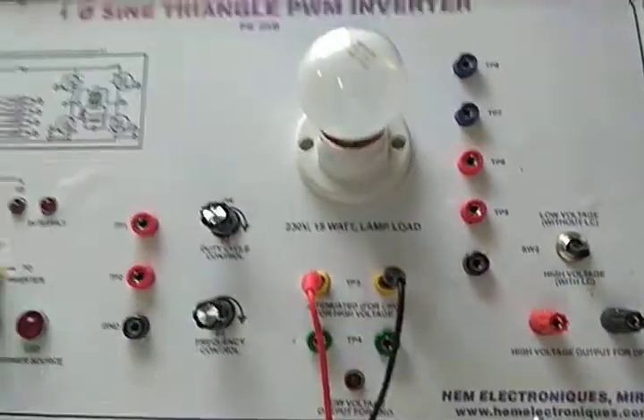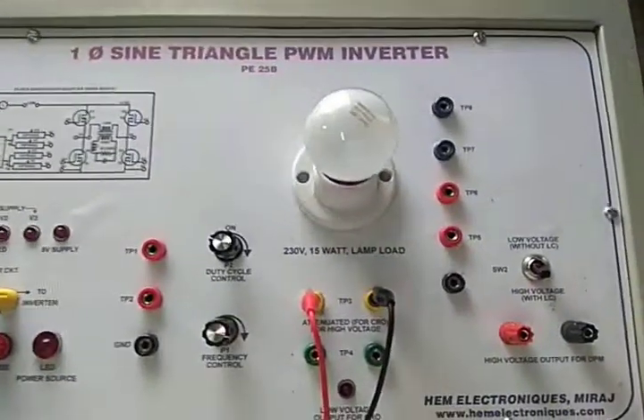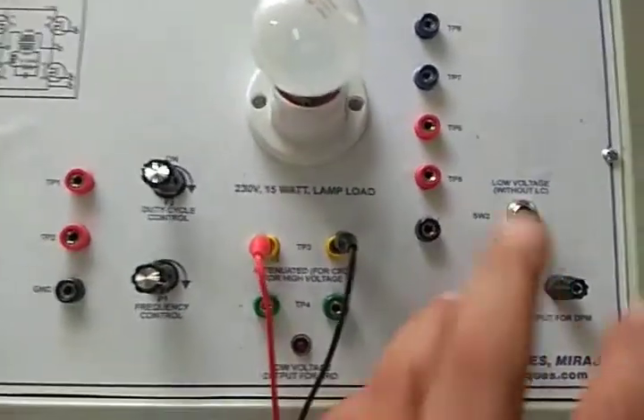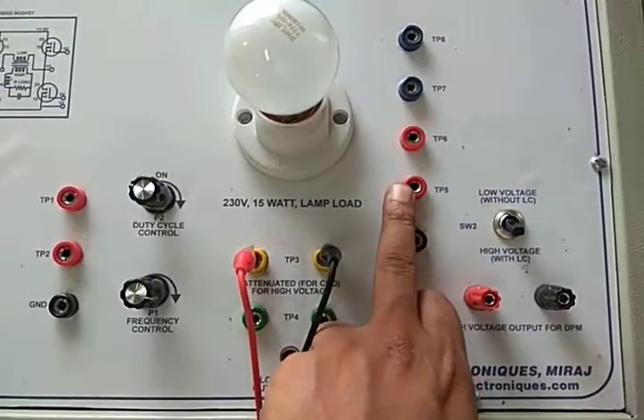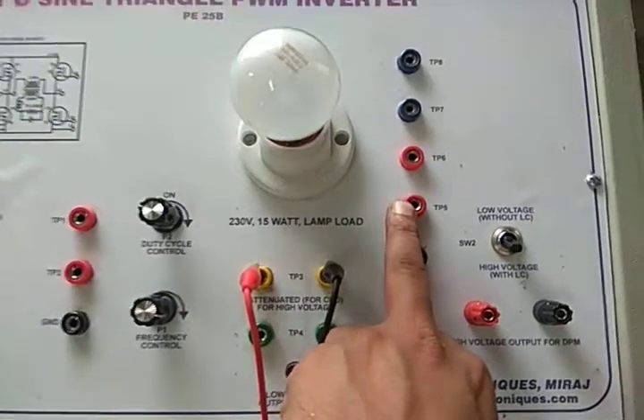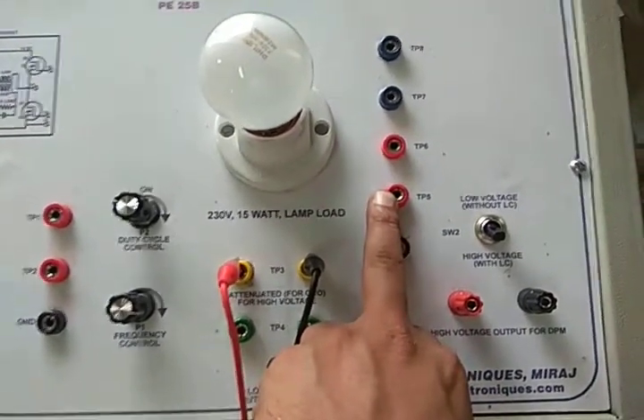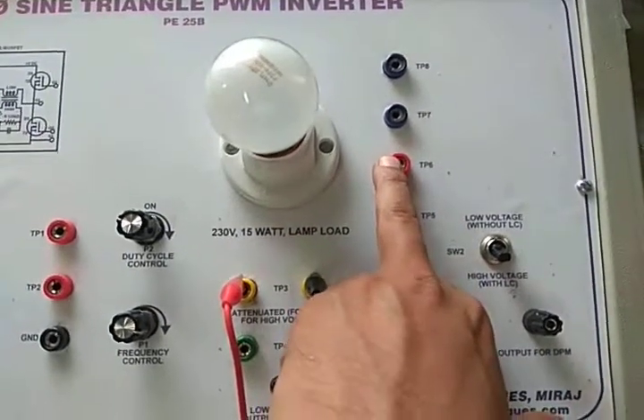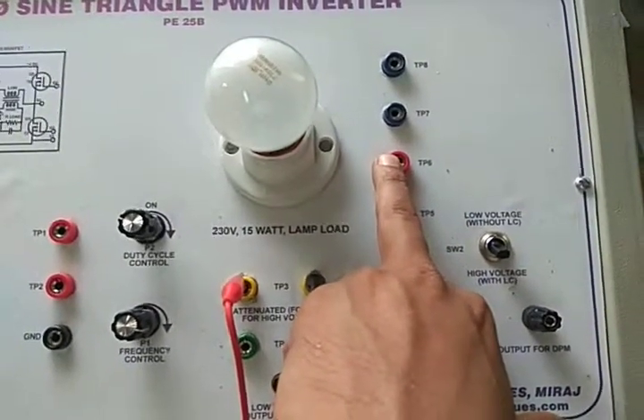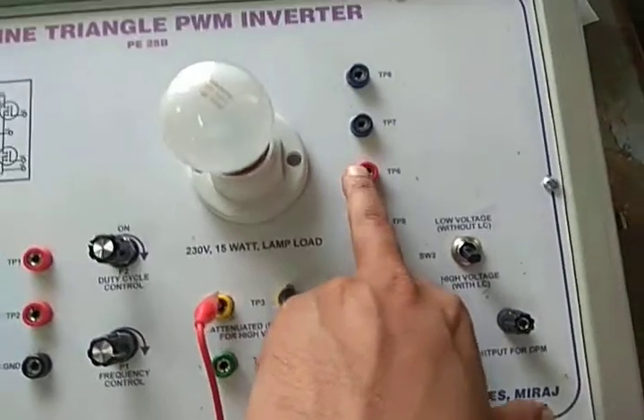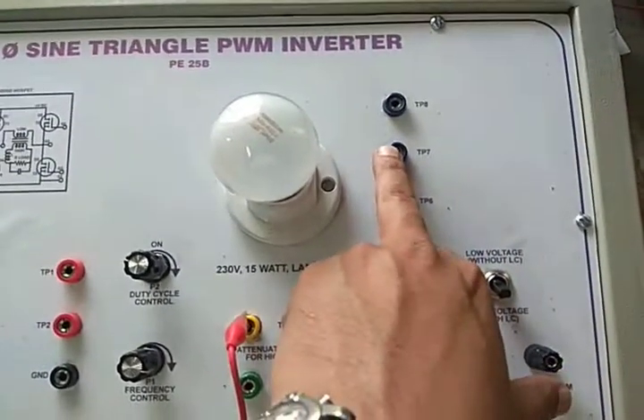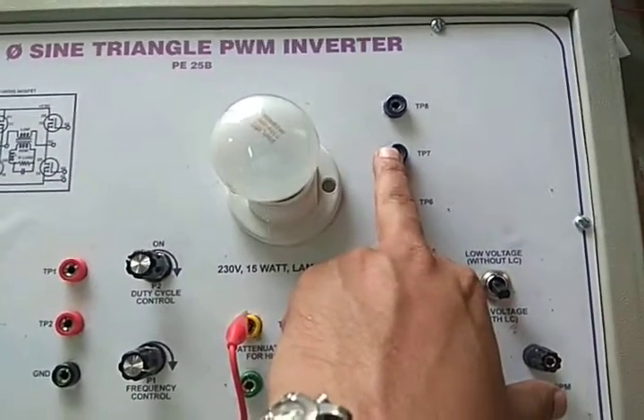The output frequency changes in the range of around 35 Hz to 50 Hz. At TP5 we have the fundamental frequency or reference sine wave, 36 Hz to 50 Hz. Then the reference or carrier frequency triangle waveform is around 1.25 kilohertz, with a triangle for the positive half cycle and a triangle for the negative half cycle.